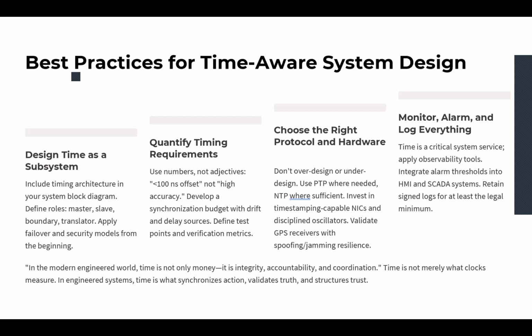How do we select appropriately? We use PTP when you need nanosecond accuracy and can afford timestamp-capable hardware. We use NTP when millisecond resolution is good enough, and the security features are more important than precision. We use IRIG for legacy systems where a serial time code is needed with minimal setup. Or we use 1 PPS in a hybrid system with low processing power.